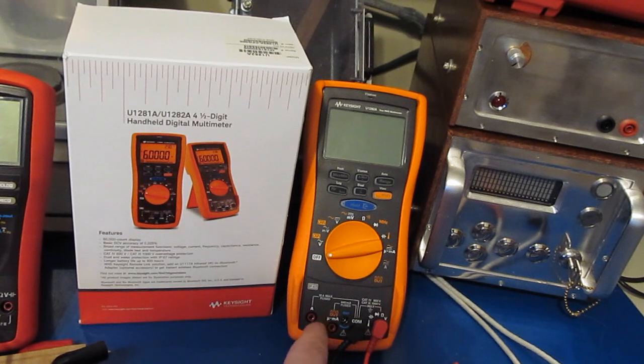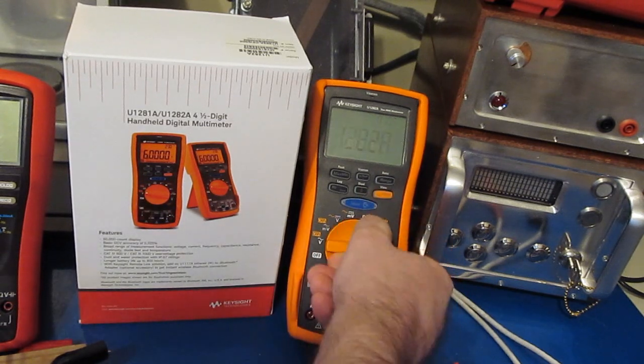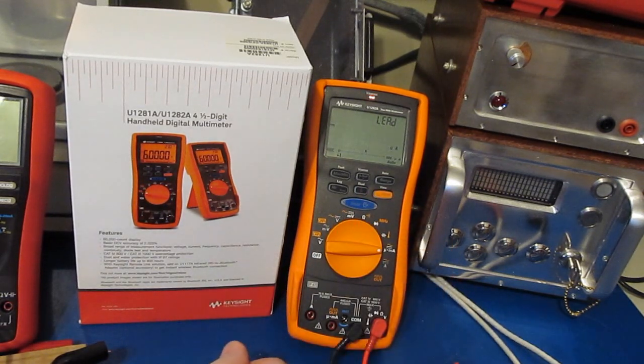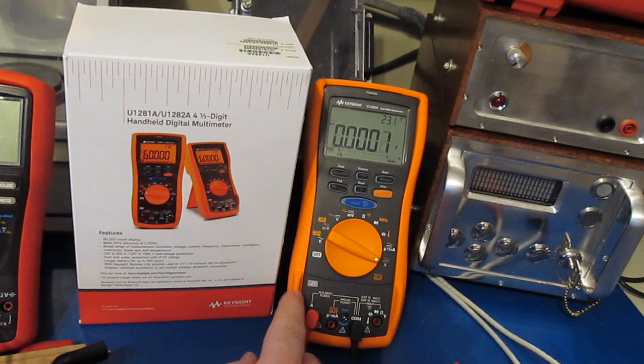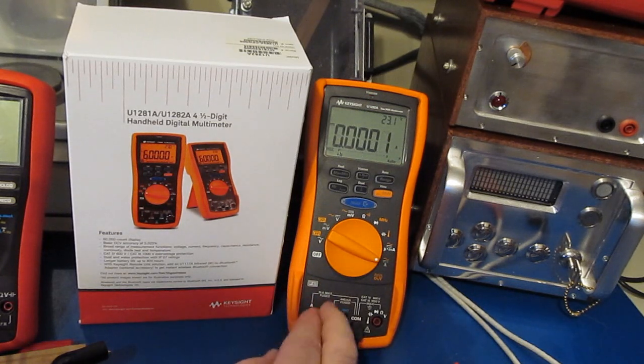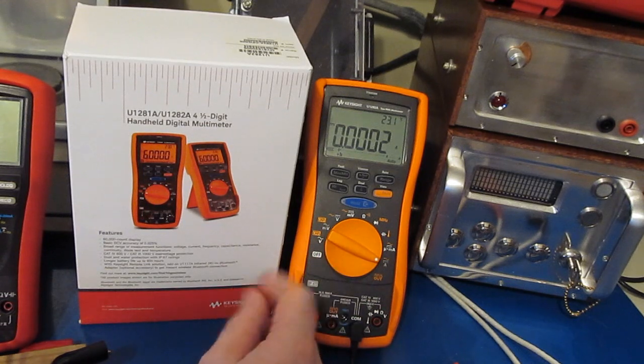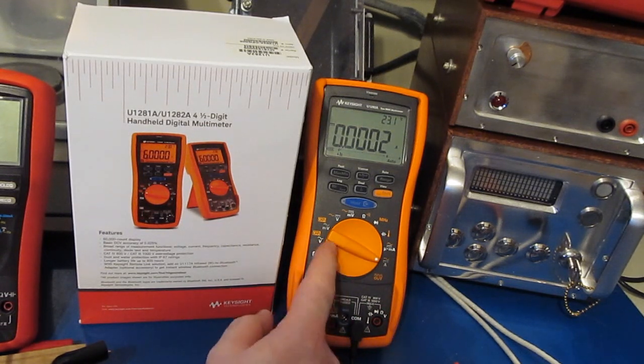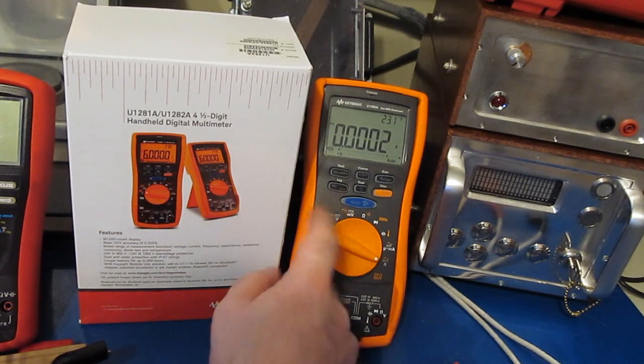This particular meter has sensors built in that let you know if you have the leads in the right positions. The way that sensor works is they have to take the voltage, in this case 2000 volts, and drop it down to something that they can actually read. For this particular design, they use a 2.5 meg ohm resistor between this jack and that sensor circuit.